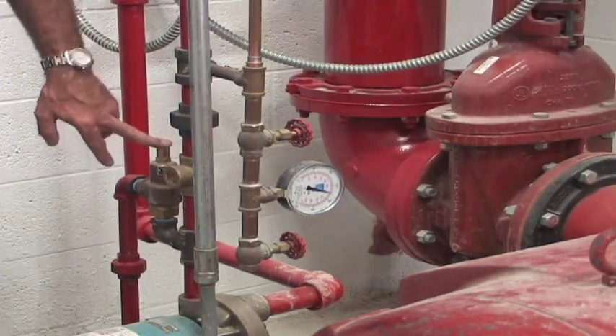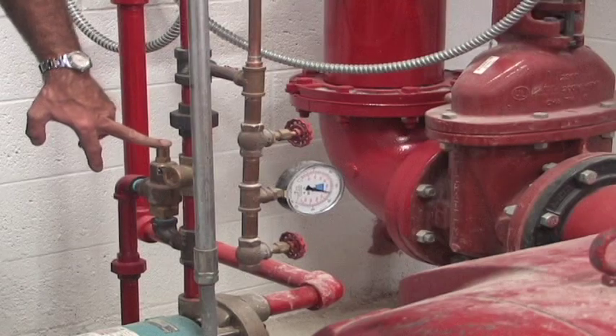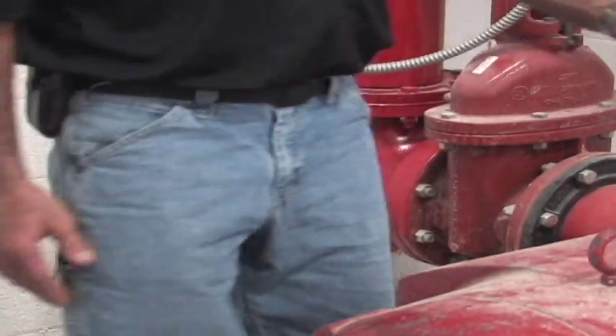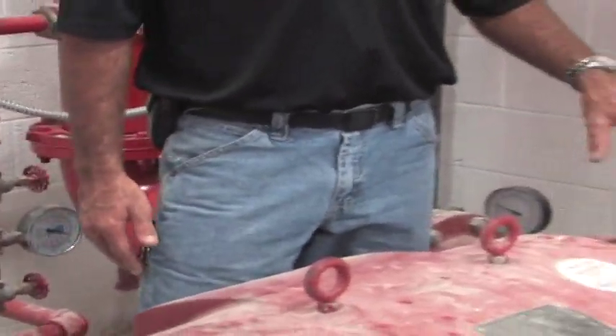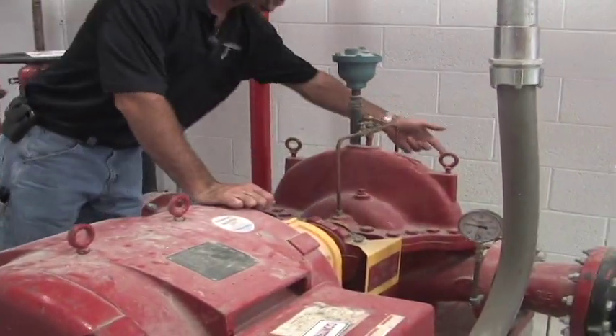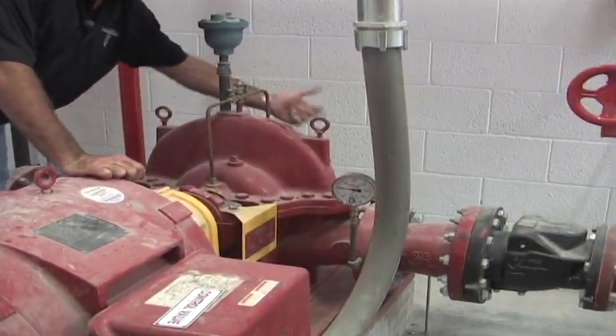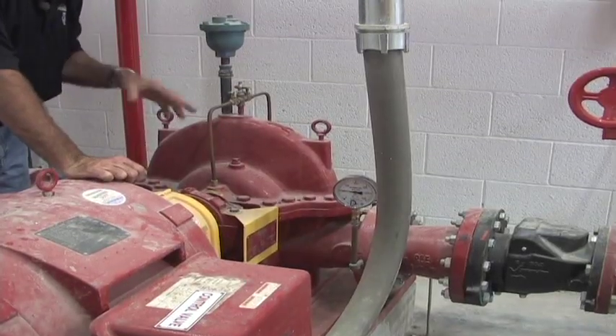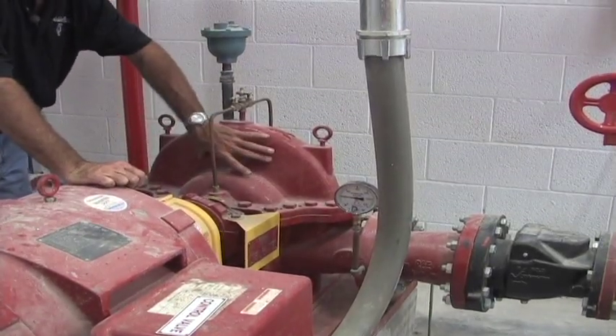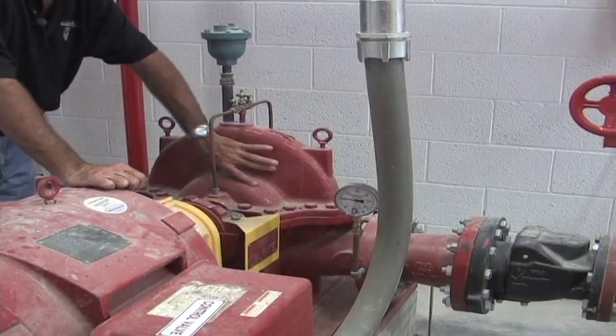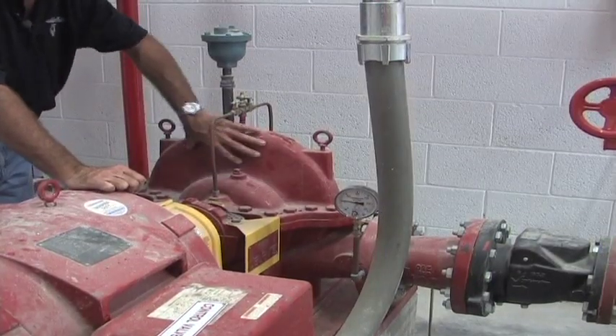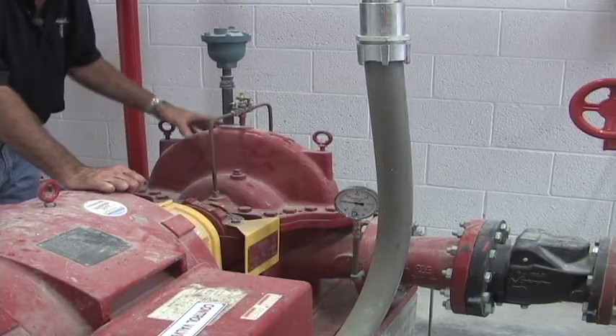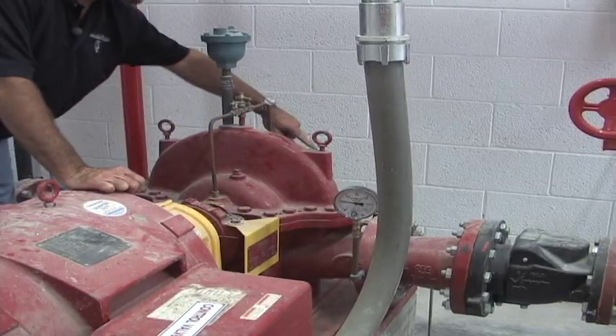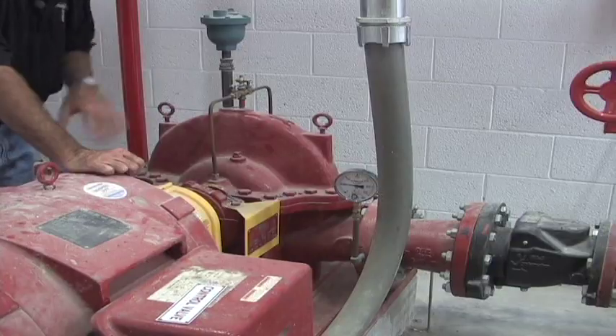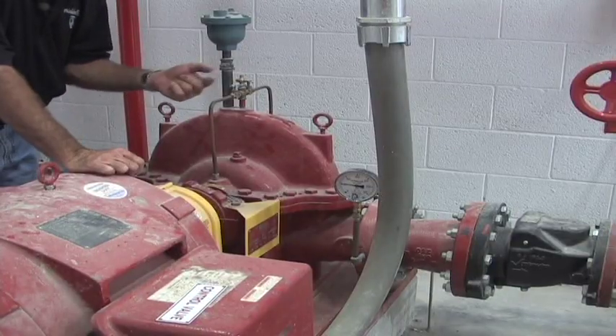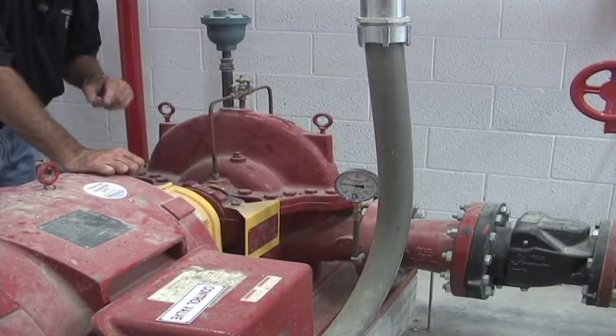The jockey pump one will hardly ever be used. When your fire pump runs, when it's at its churn pressure where you're not flowing any water, you will see water coming out of the discharge pressure relief valve and dumping outside. That's going to keep this water from inside here from getting hot. During your 10-minute run cycle, as you're running the pump, you're always going to want to keep your hands up here and feel it. Make sure we're not getting hot inside the head. We're going to make sure that your relief valve is always dumping water. Every time we start this up, first thing we're going to want to do is walk outside and make sure that our relief valve is dumping water out.